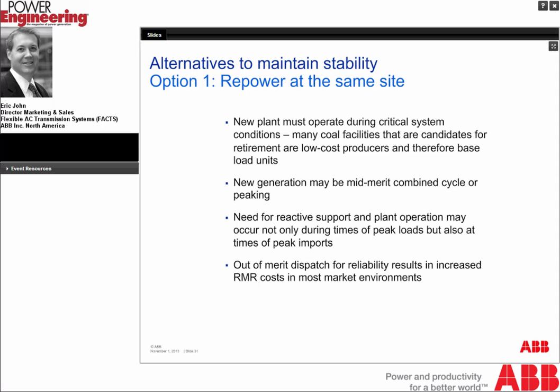So drilling down into option one, repowering at the same site, this seems fairly straightforward. If you have a power plant, you can reuse the existing transmission and possibly the transportation facilities and repower by building a new power plant. But there's some caveats to this, and the first is that the new plant must operate during critical system conditions. Most of the coal facilities that we're talking about today that are candidates for retirement are the low-cost producers, and therefore they're baseload units. That means they run 24/7 because they're low cost, and as a corollary to that, they're also available to be called upon to provide that dynamic reactive support following basically any system condition. They're always running because they're low cost, and therefore, regardless of what contingency comes up, they can be thought of as an anchor to the system.